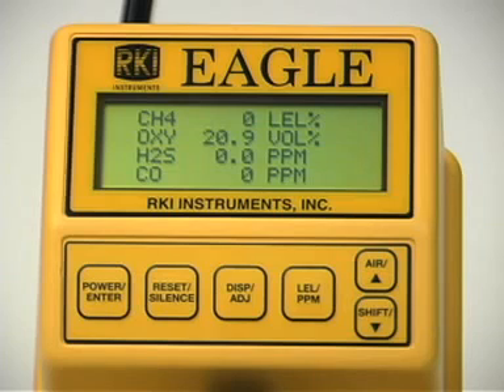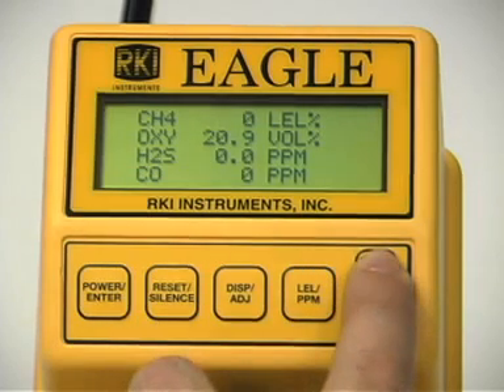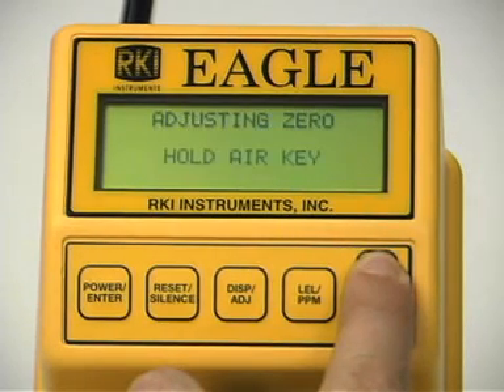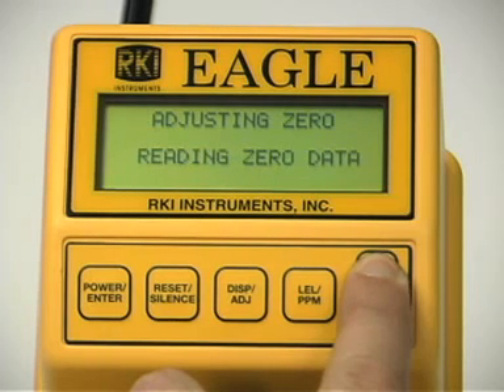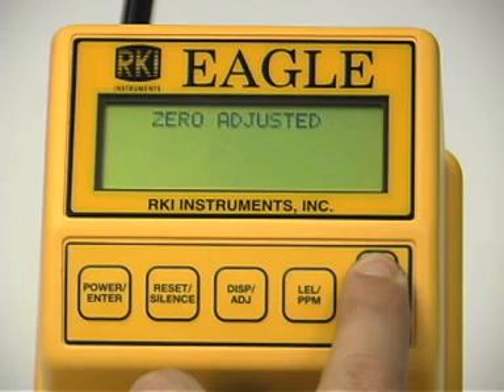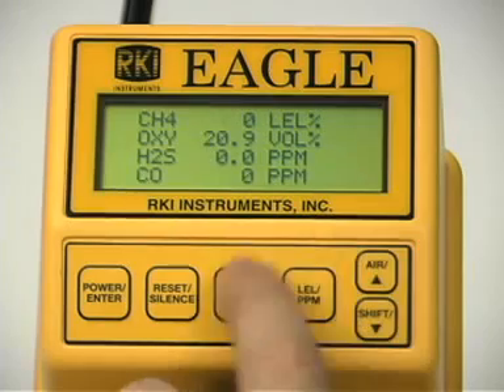Take the Eagle to a non-hazardous location with fresh air conditions. Turn on the Eagle and allow 1 minute for warm-up. Perform a demand 0 by pressing and holding the air button until the display instructs you to release the air key. This automatically sets the combustible gas and toxic circuits to 0 and the oxygen circuit to 20.9%.